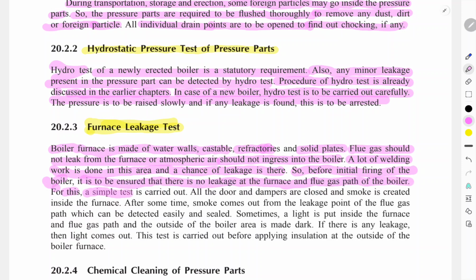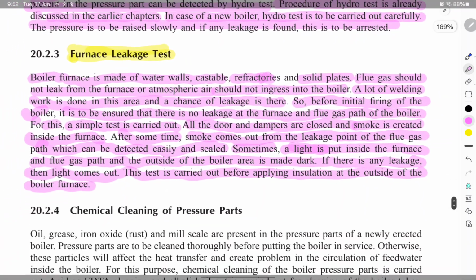For this, a simple test is carried out. All doors and dampers are closed and smoke is created inside the furnace. After some time, smoke comes out from the leakage joints in the flue gas path, which can be detected easily and sealed. Sometimes a light is put inside the furnace and flue gas path, and the outside of the boiler area is made dark. If there is any leakage, then the light comes out. The test is carried out before applying insulation on the outside of the boiler furnace. So this is our furnace leak test.